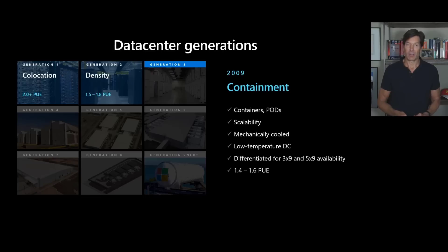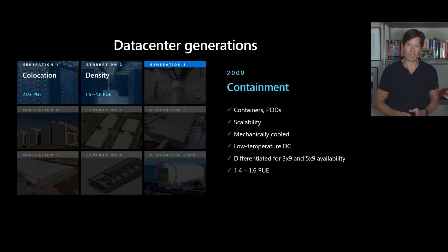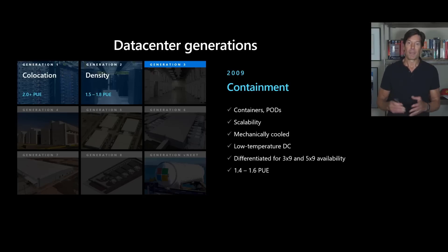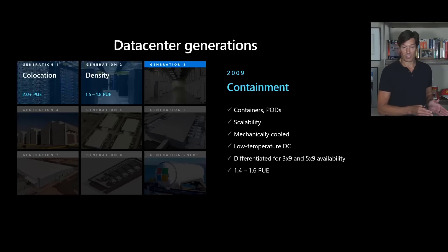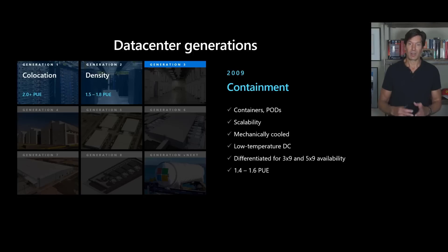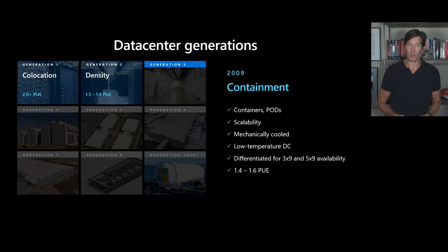With generation three, our container phase, we focused on deploying containers of servers. This allowed us to move more quickly and also to segregate three-nines capacity from five-nines. Five-nines capacity — gold-plated, with dual redundant power cords to every server — has higher PUEs than three-nines containers, where we could run workloads more resilient to total failures. In fact, Office services today are designed to work in three-nines configurations such that even a whole region can go down and Office 365 customers will see no impact. This got us down to PUEs of 1.4 to 1.6.